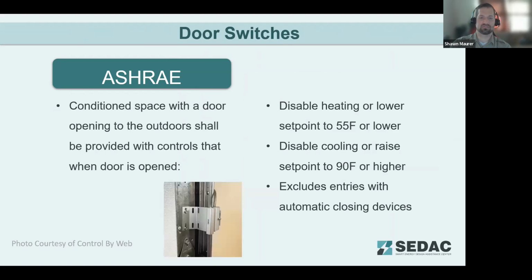I did have a request here real quick for the door switch control. Someone wanted me to show that again, so before I move on, we'll jump back to that screen. Again, in ASHRAE, it's not yet implemented in the IECC. If you're going to have a space that's seasonally allowed to be an outdoor space, then you have to have the ability to either disable the heating and cooling system or turn those set points back to a neutral set point to minimize energy consumption.